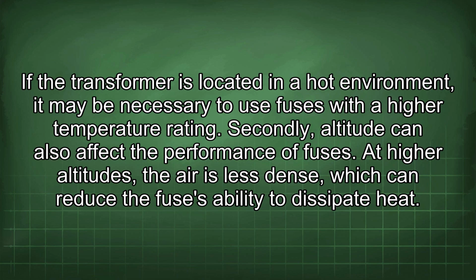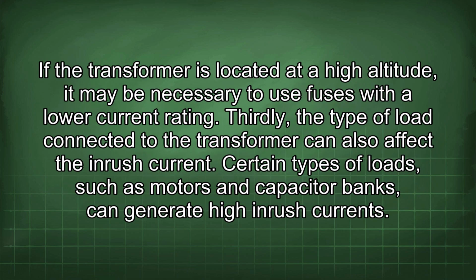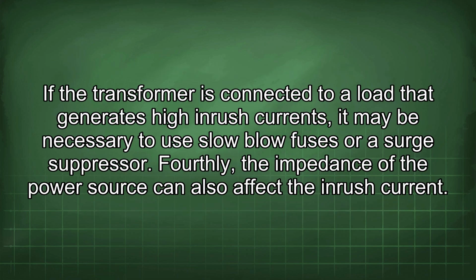At higher altitudes, the air is less dense, which can reduce the fuse's ability to dissipate heat. If the transformer is located at a high altitude, it may be necessary to use fuses with a low current rating. Thirdly, the type of load connected to the transformer can also affect the inrush current. Certain types of loads, such as motors and capacitor banks, can generate high inrush currents. If the transformer is connected to a load that generates high inrush currents, it may be necessary to use slow blow fuses or a surge suppressor.